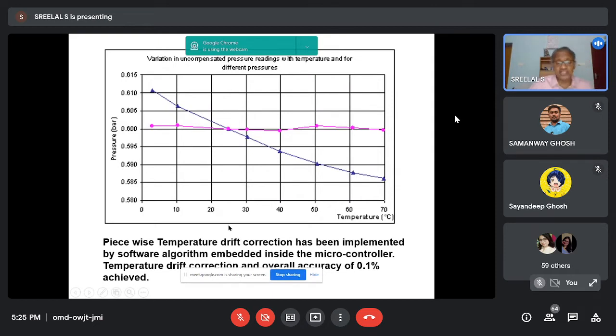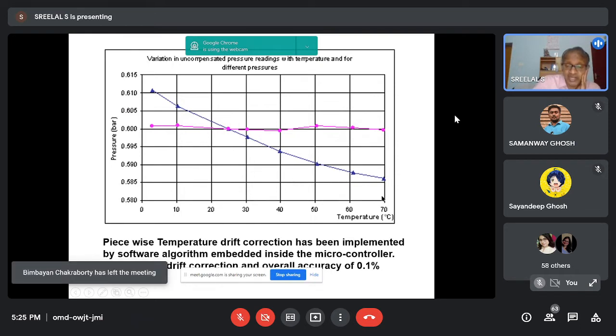Now, what is temperature compensation that we mentioned? It is one of the basic data processing techniques useful especially with pressure sensors. In the case of a normal pressure sensor, when temperature is varied, the pressure reading will also vary. As the blue curve shows, the pressure reading varies according to temperature also.